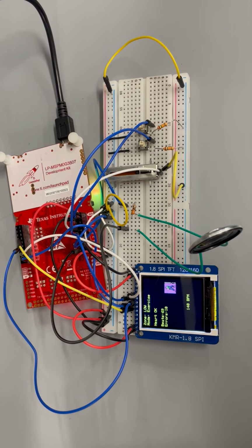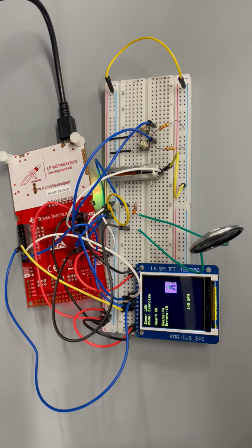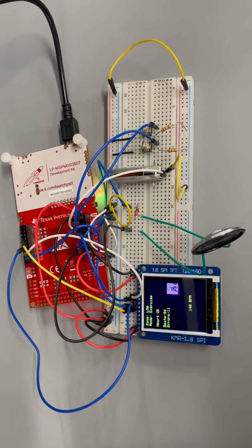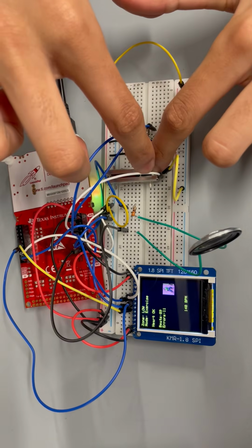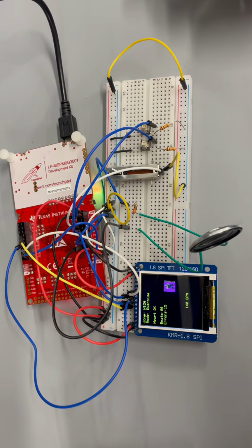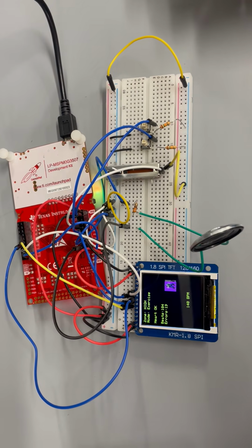Another thing we can do is change the mode from resting to exercise. So that's going to increase the heart rate a lot. And even now there's going to be a few more errors because the heart's beating faster. And then if we move this to high, there's going to be a lot of missed beats because we're going at a very, very high rate.